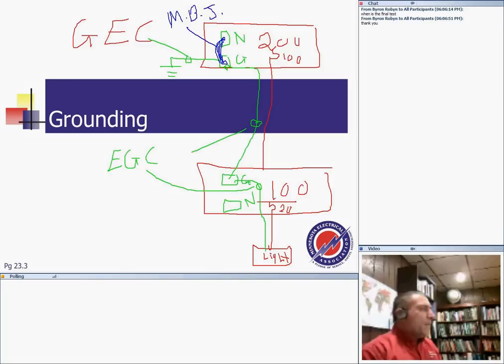So we have main bonding. This is the service. I want to bring to your attention, this is my service here. Service, inverter, and this is my sub panel. I'm showing a 200 amp; it could be 2000 amp feeding a 1000 amp. The same way: ground conductor, equipment grounding conductor, and main bonding jumper. There are a few other things I want to leave for another time.